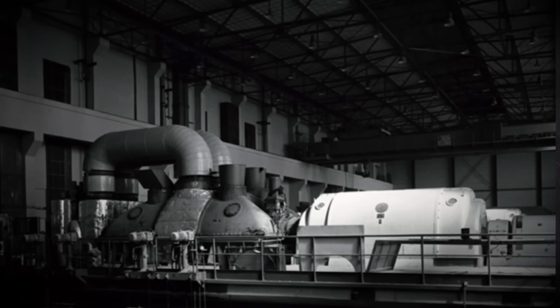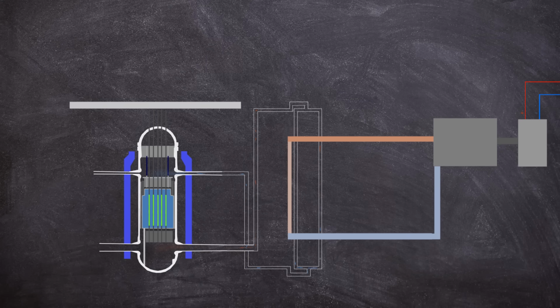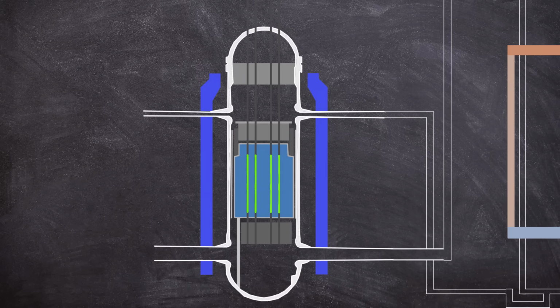But let's have a look at how the reactor worked. The A1 reactor was a gaseous CO2 cooled, heavy water moderated system. The reactor core was within a pressure vessel made of 15 centimeter thick carbon steel in a cylindrical shape, with a diameter of 5.1 meters and a height of 20 meters.